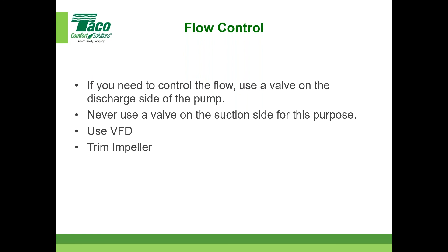You could trim the impeller. We don't see that too often, but there are cases out there where people might suggest you trim the impeller. In that regard, if you're going to put a VFD on, do you need a trimmed impeller? Well, there are different thoughts on that. I don't want to get into that whole discussion. We talked about that during VFDs. My feeling is, as long as the design point is close to maximum impeller size, maximum trim, I don't mind using the VFD with a full trim impeller. That gives me some flexibility there. But if that design point is maybe below halfway down the impeller trim, personally, I would maybe go in a different direction and trim that impeller to some value. But nonetheless, that's another whole discussion. Talk to your folks at your company, or take a rep and get their opinion on that. I think there are 2 sides to that. There might be 4 sides to that discussion.